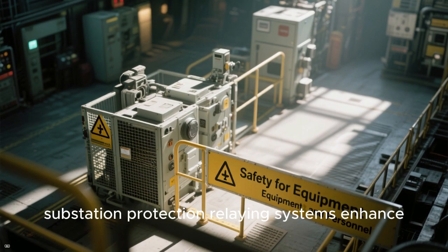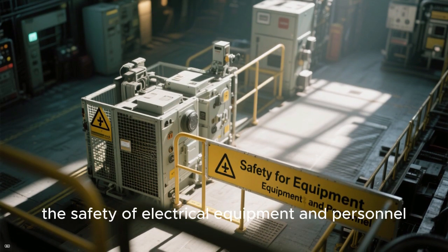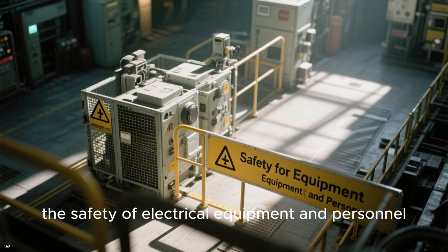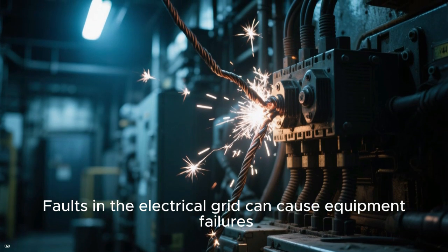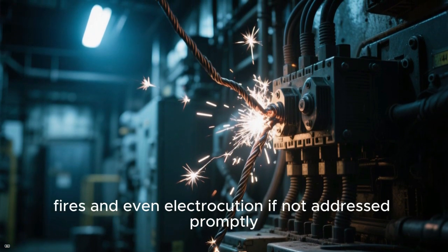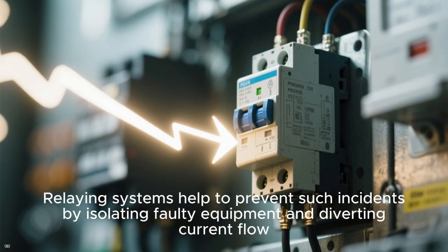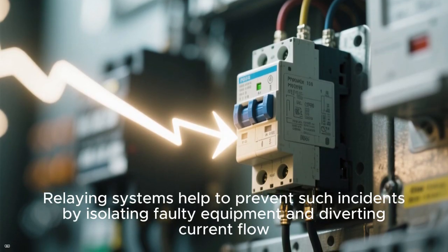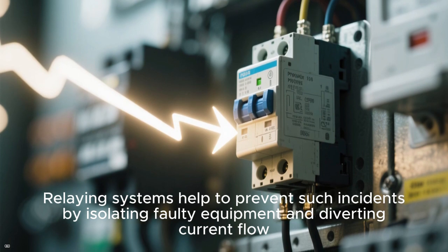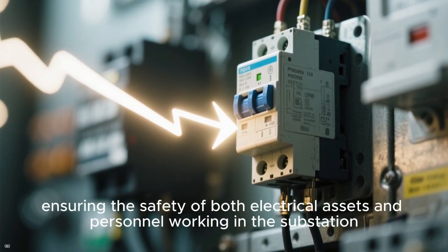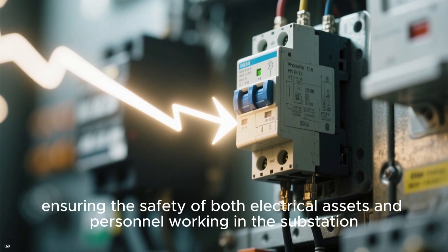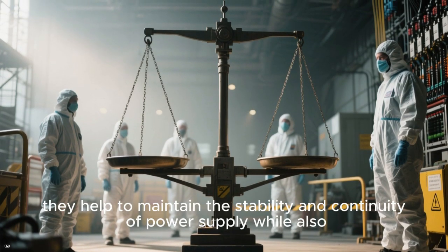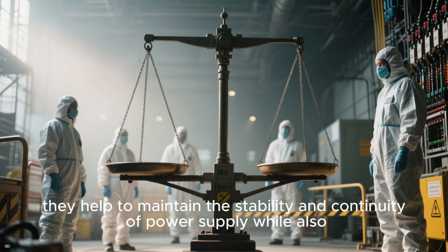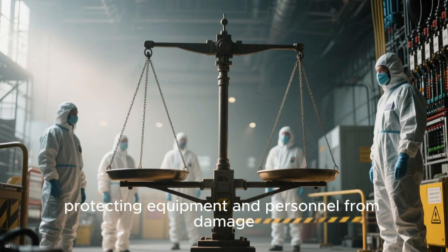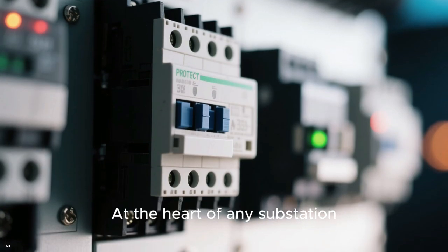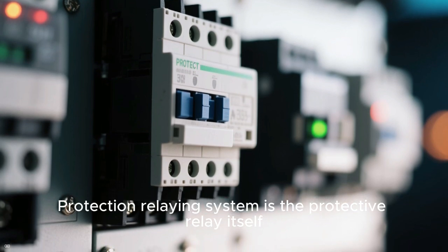Furthermore, substation protection relaying systems enhance the safety of electrical equipment and personnel. Faults in the electrical grid can cause equipment failures, fires, and even electrocution if not addressed promptly. Relaying systems help to prevent such incidents by isolating faulty equipment and diverting current flow, ensuring the safety of both electrical assets and personnel working in the substation. By doing so, they help to maintain the stability and continuity of power supply while also protecting equipment and personnel from damage. At the heart of any substation protection relaying system is the protective relay itself.